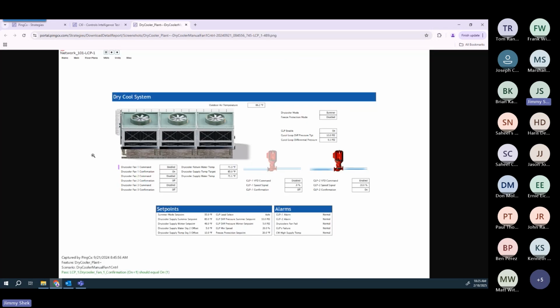On the right-hand side here, you'll see that we are able to take a screenshot. As mentioned before, during these tests we have the ability to go out and take screen captures of the graphics from the BMS system. Many times, when we're working with commissioning agents as we're running these tests, they always like, oh, let's take a screenshot of it. For one, it gives you a visual confirmation that the points you're dealing with are also mapped correctly to the graphics. In this case, we're overriding the fan 1 command to be enabled and checking the fan 1 confirmation. It also provides additional points related to that unit, so they have those values at that point in time, and there's no need to sit there and copy the values and fill out their testing forms while you're going through this step. So it provides that documentation as part of this process.